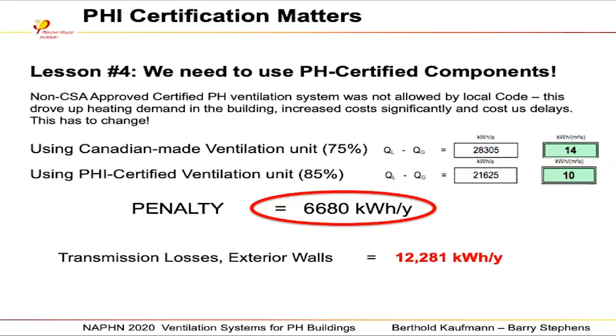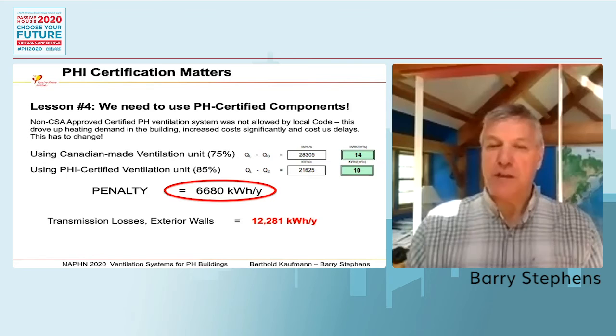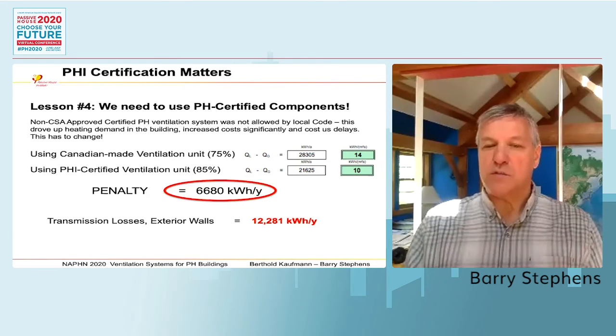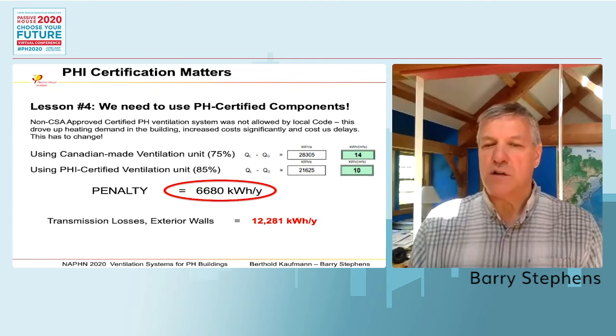And when you look at just that 10% difference, what you're looking at on the right is the difference in the demand. It's a 40% difference. You're going from 14 down to 10 on your load there, your requirement, and just by that 10% difference in ventilation efficiency. And the penalty between those was 6,600 kilowatt hours a year.